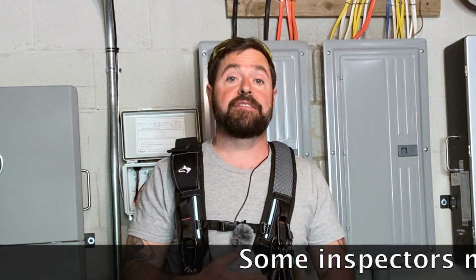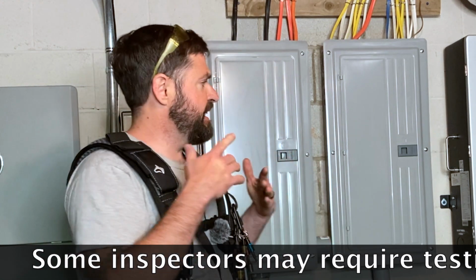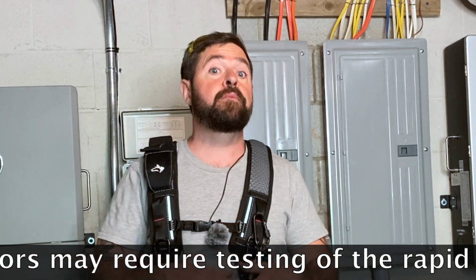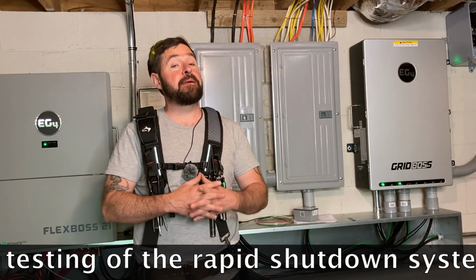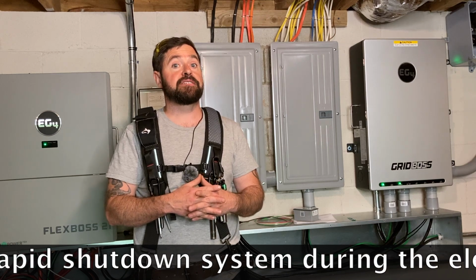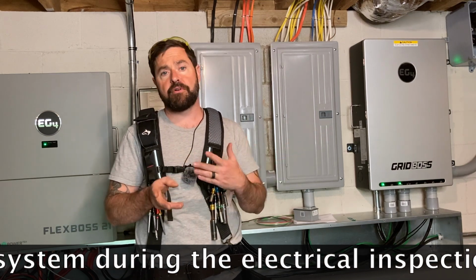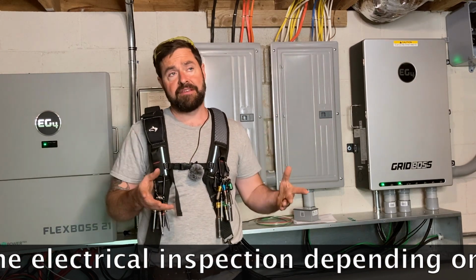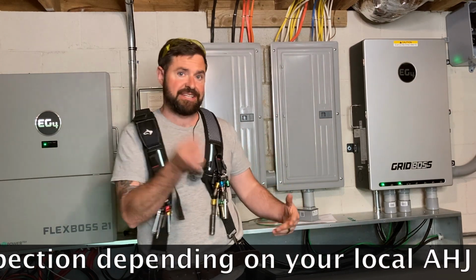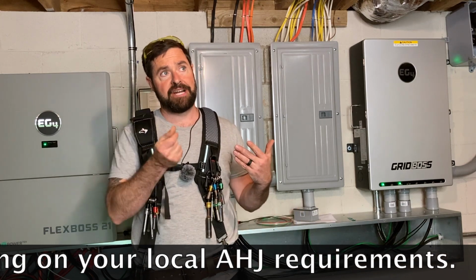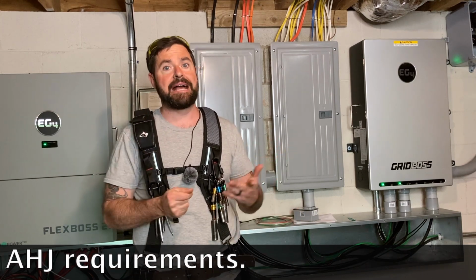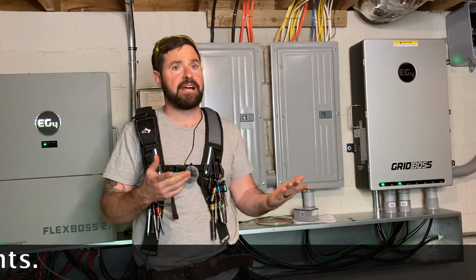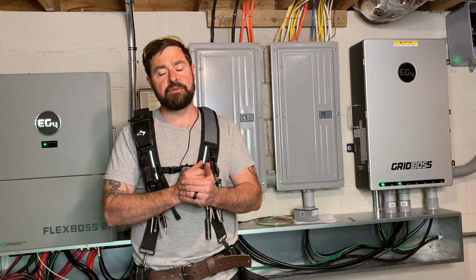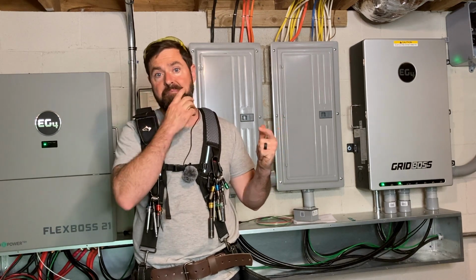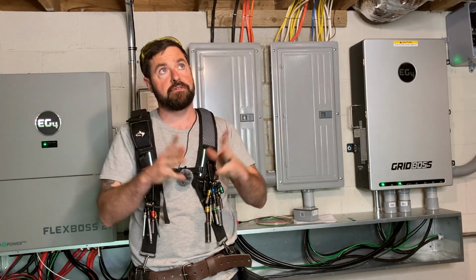Some of you may have seen the episode where I tested the rapid shutdown switch and it actually turned off my critical loads in my home. A viewer pointed out that maybe because I didn't have grid assist set up, when I hit the rapid shutdown, the house's power goes out instead of instantaneously pulling from the grid. It shuts down for about 10 seconds and then comes back on. That resets my internet, which is kind of annoying, and resets all the clocks. Most systems will just seamlessly trip over to the grid within milliseconds, and you can barely see your lights flicker.